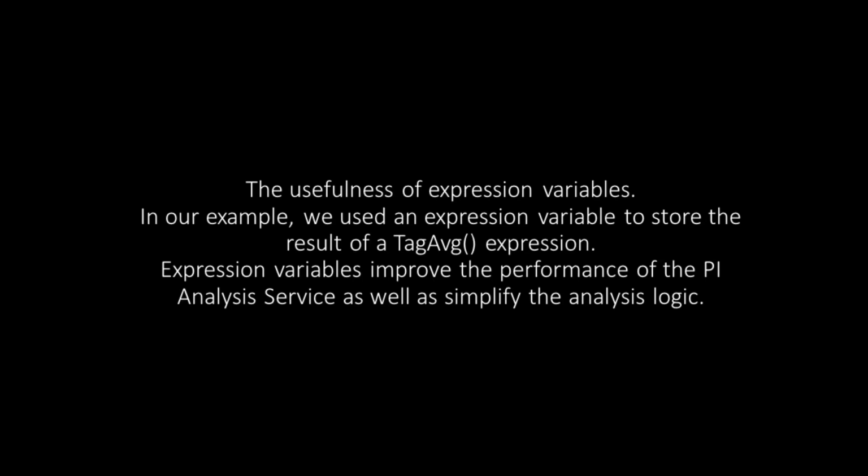So in the production environment, we'd set up a variable to run that tag average value, and then we reuse the variable in multiple steps. So by splitting up your calculation into multiple variables, not only is it easier to read, easier to troubleshoot, it can also improve the performance by reducing the number of calls for data to the data archive.